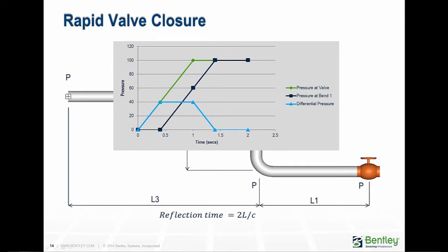If the wave returns to the valve before the valve is fully closed, for example in a relatively short system, then the maximum pressure rise calculated by Joukowsky for the complete valve closure cannot be achieved, as the fluid flow will continue through the partially closed valve. In this case, the approach is conservative, and AutoPIPE will report a warning to that effect.